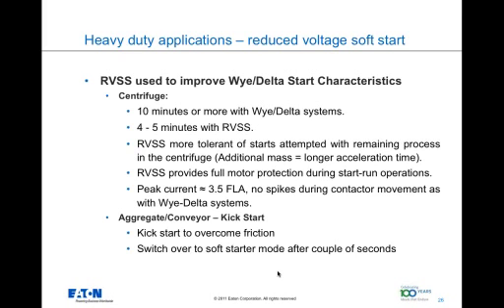Similarly, for starting an aggregate system where there is a high initial load and friction, the kickstart feature in a soft starter can be used to overcome friction and also to provide the needed higher torque. After the motor gets going, it is then switched to a soft starter mode. The kickstart basically gives the initial oomph to get the motor going. Once the motor is going, the configuration can switch into a soft starter mode. Such a feature is not available when you have a wye-delta configuration or across the line configuration.